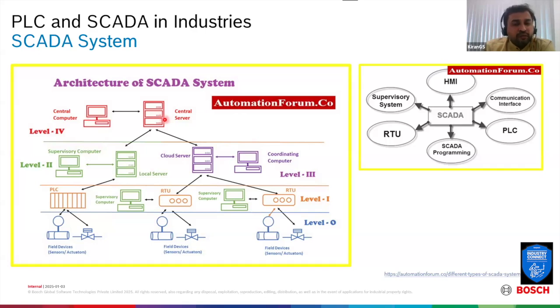From this angle, the architecture of a typical SCADA system first has a basic requirement of data acquisition and control. But at the same time it has multiple options to share the data — we can share PLC one's data with another, or from RTU one back to the PLC. These things are possible. It also gives flexibility for redundancy, meaning if one server goes down, the others can take care of it.